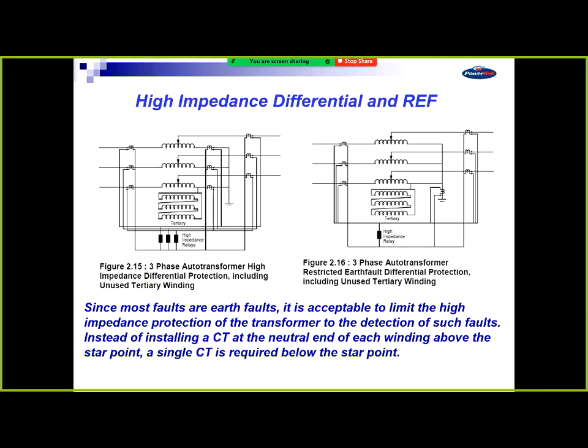What is another common thing which we use at times, maybe a bit less nowadays, but recently we've been using quite a lot, is what's called an REF, high impedance scheme, a restricted earth fault. So that neutral CT, that star point CT is below the star point, so it's just in the neutral. So all 3 phases are summed together and the neutral point get together, so it's just looking at earth faults. So what this will do is detect low-level earth faults. And what we've been doing is inside the transformer, in the turrets, we get some CTs put in. They're all the same ratio, and in that neutral point, get a CT put in there. And we put a restricted earth fault around in there. So we're detecting low-level internal faults in the transformer.